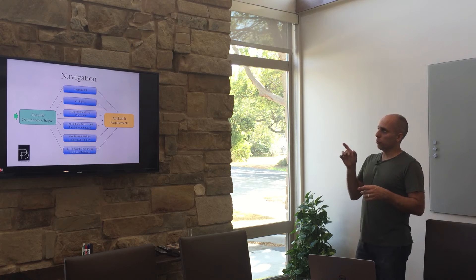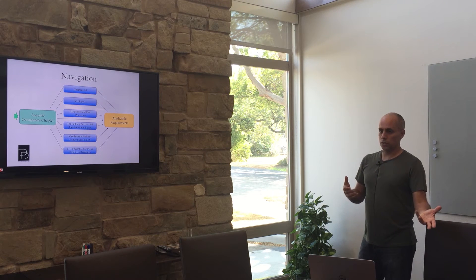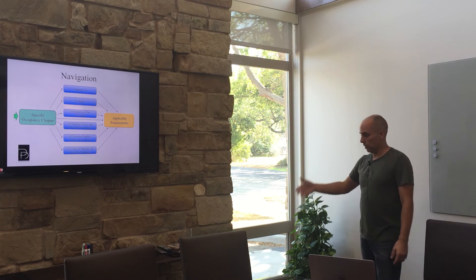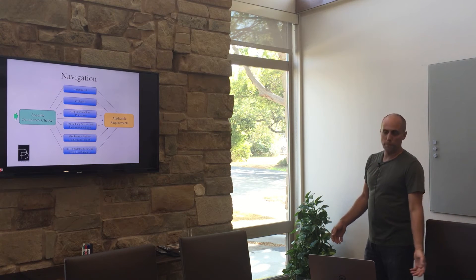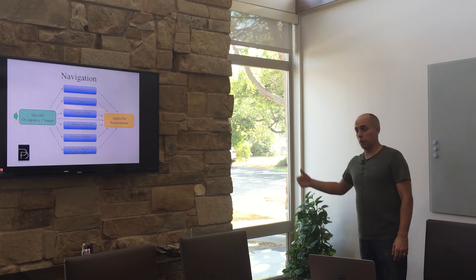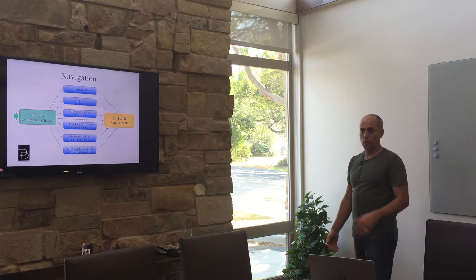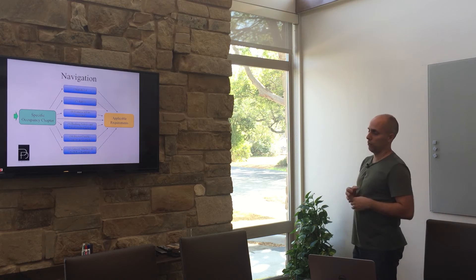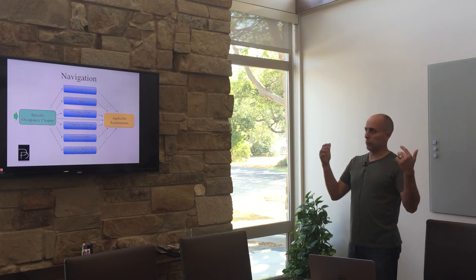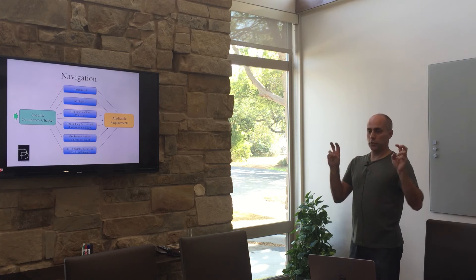One of the biggest misconceptions is: 'Chapter 7 egress is there, so it all applies — I can pick any section from chapter 7 and require it.' That is only valid if required by the occupancy-specific chapter, because requirements may be modified, restricted, or simply not applicable. Chapter 7 does not apply to everything, and neither does chapter 9 — only if the parent occupancy-specific chapter tells you it does.